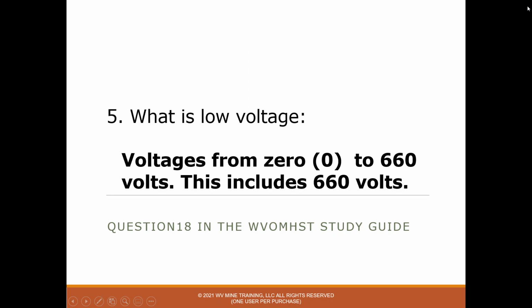Number 5, what is low voltage? And the answer is voltage is from 0 to 660 volts, and this does include 660 volts. So you have low voltage equipment at your mine. What comes to mind is roof bolters and shuttle cars are typically either 480 volts or 575, but both of them are less than 660, so they're low voltage equipment. Maybe chargers, scoop battery chargers are usually 480 or 575, so that's low voltage.